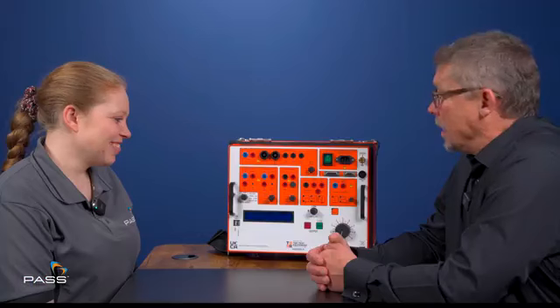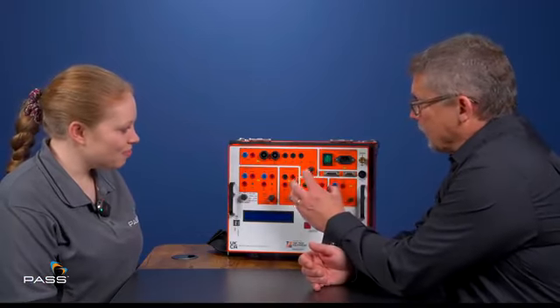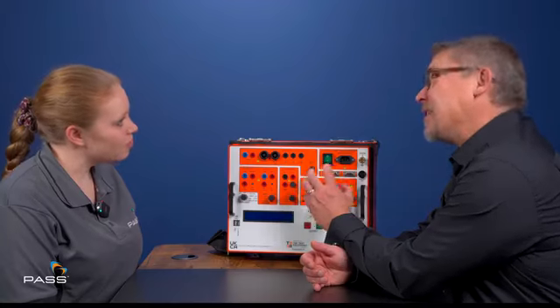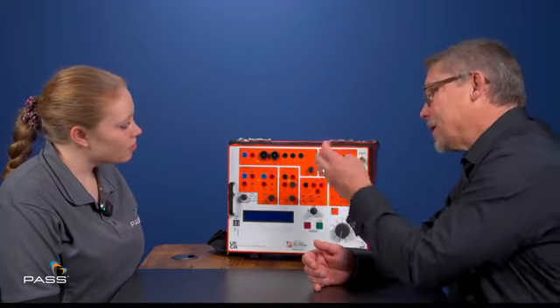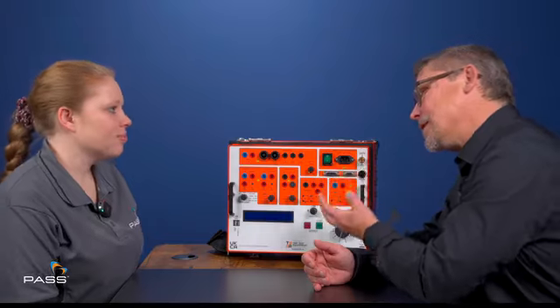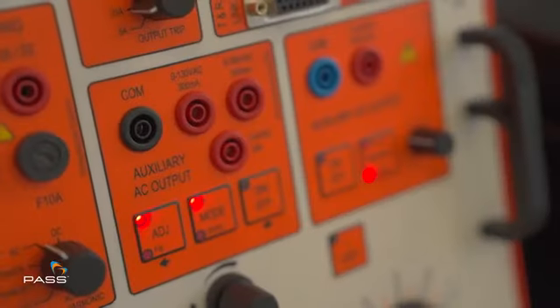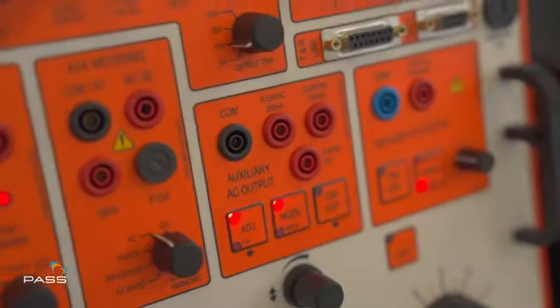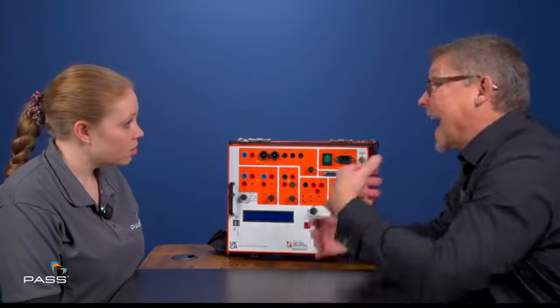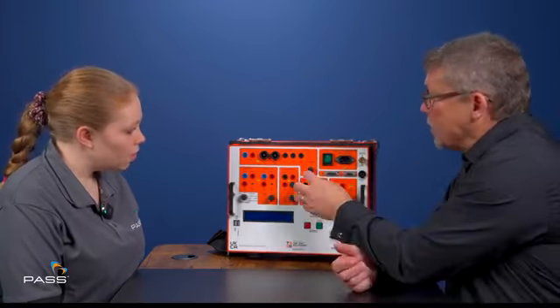Very, very simple. So the next part that really differentiates this machine from other SCITs and makes it a little bit even more blurred, because as I mentioned, having 200 amps, is it a secondary, is it a primary? Having this auxiliary channel changes things completely. The auxiliary channel will give me a secondary output, and that secondary output will give me either voltage or current. It'll give me voltage to 300 volts or current to 10 amps. And I think I'm correct in saying there's not another SCIT that will give you 2 channels of current without an auxiliary extra device that you buy. So that's a big advantage.